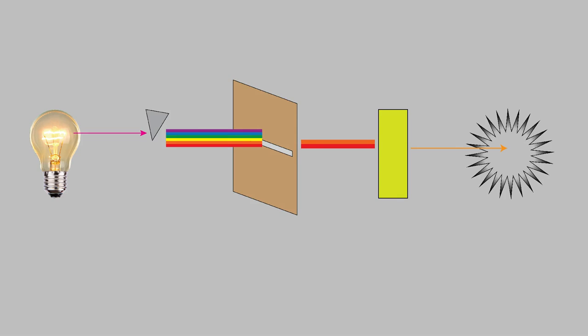One solution would be to narrow the slit so that we can select a smaller and smaller wavelength range. But there are two problems with this idea. First, if we make the slit narrower that means less light will get through overall, so unless we make the light source much more powerful the intensity of light that hits the sample will decrease. That could make the light too faint for our detector and could also prevent the sample from reacting with the light if there's a photochemical reaction we want to cause.